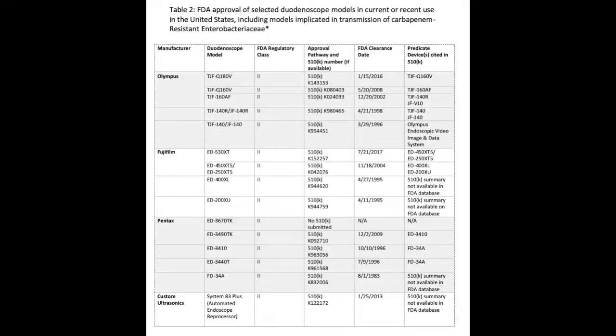We evaluated data reviewed by FDA to support clearance of selected duodenoscope models. We documented the predicate devices to which substantial equivalence was claimed and traced these devices back in time. In Table 2, we show the various duodenoscope models from all three manufacturers, their approval dates, and the predicate device for substantial equivalence.